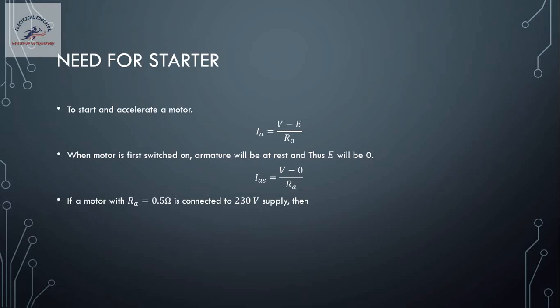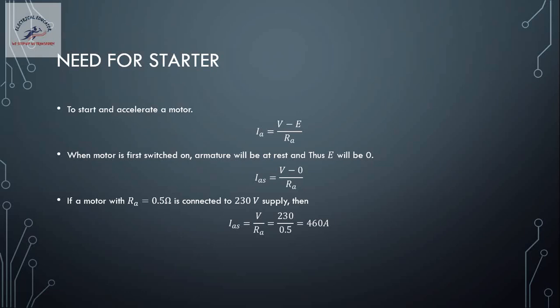Let us take an example. Consider a DC motor whose armature resistance is 0.5 ohms connected to a 230-volt supply. With the motor at rest and back EMF zero, the starting current = 230 / 0.5 = 460 amperes. This is a very large current, and this amount of current flowing in a small 230-volt motor is very dangerous — it can damage the armature and burn the windings. It is therefore necessary to limit the starting current to the maximum permissible value, and starters are used for this.